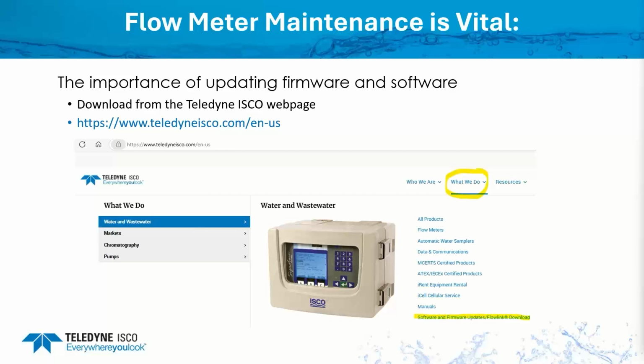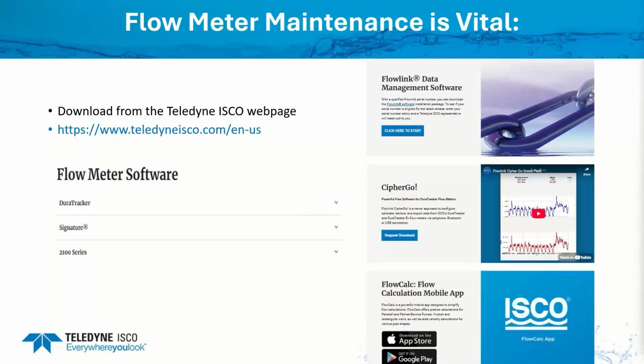So you may be wondering, where do you get the firmware and the software bin files? If you go to our website, teledyneisco.com, there's several ways to get to it, but what I like to use is just go to the What We Do, and you'll see down here at the bottom is the software firmware updates. And that will take you to the next page, which then you can drive down and see the flowmeter software, the different modules, so the DuraTracker or Signature, and when you drop that down, then it'll break it down even further into the individual sensors, like the laser flow sensor, the 350 AV sensor. So you'll have a list of all your bin files that you need for the firmware updates.